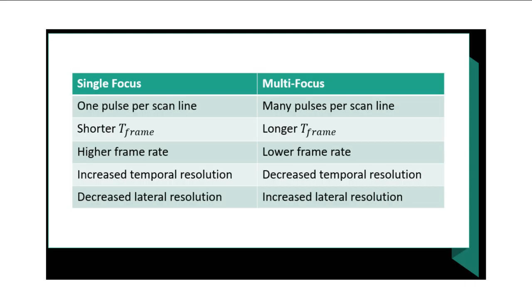With single focus: one pulse per scan line, shorter T-frame, higher frame rate, better temporal resolution, but decreased lateral resolution. With multi-focus: multiple pulses per scan line, longer T-frame, lower frame rate, worse temporal resolution, but better lateral resolution. Multi-focus works better with higher frequency transducers and superficial exams — thyroid, testicle, breast — compared to deeper, lower-frequency exams.